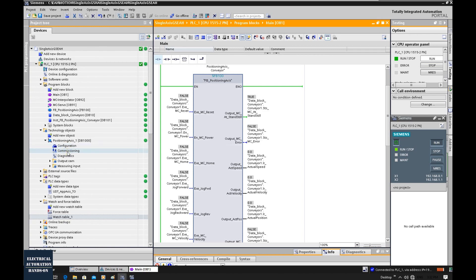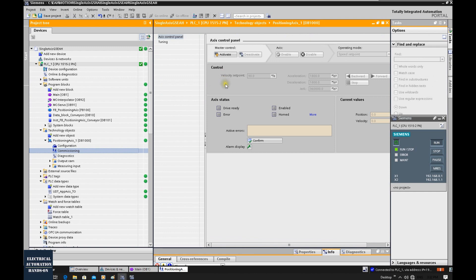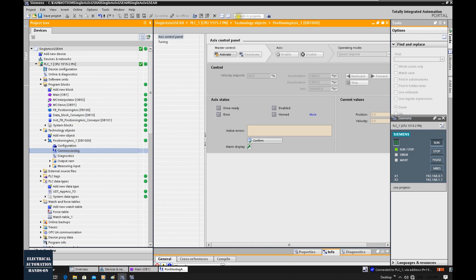Let's click commissioning and go to the control panel. Once we build up the machine and assemble all the mechanical and electrical equipment together, we need to verify the direction, verify if the speed settings make sense for this system, and ensure we won't crash the mechanical system. We need to initially test our motion system using this commissioning axis control panel.